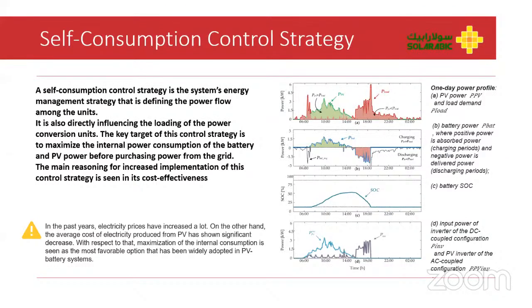The key target of the control strategy is to maximize the internal power consumption from the battery and the photovoltaics before buying the expensive energy from the grid. On the right, you see four different graphs. The first graph, A, is between the PV power and the load demand. B explains the charging and discharging profile over a period of a day. C explains the state of charge in one-day operation for that particular system. And in graph D, you see the coupling stress in terms of the loading on the inverter for the DC coupled configuration and for the AC coupled configuration.